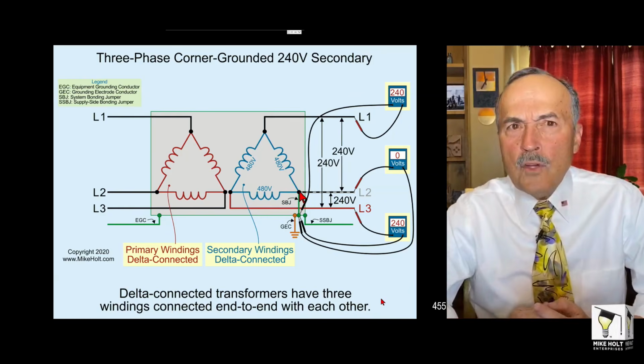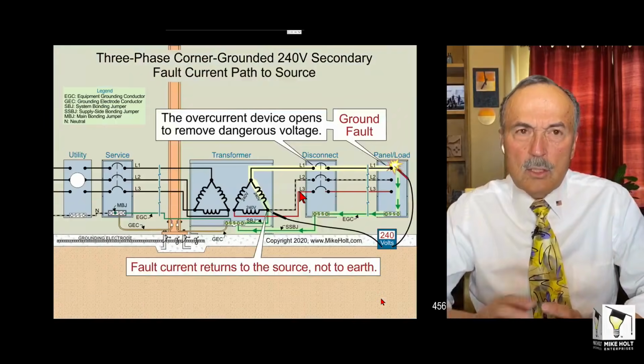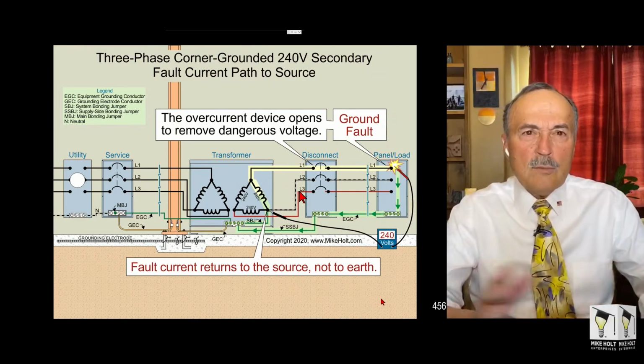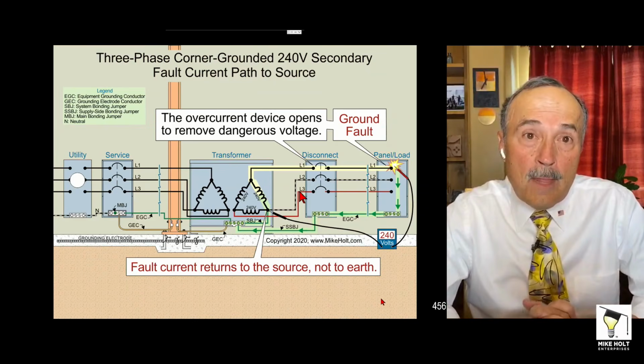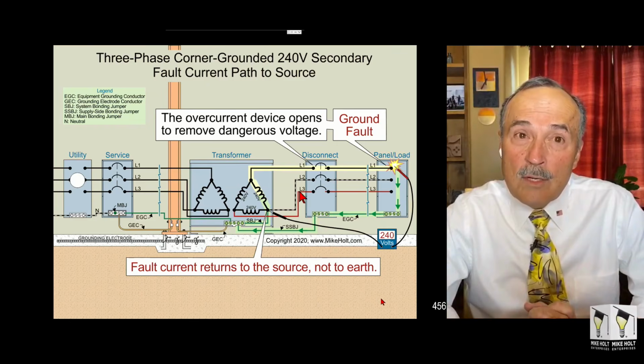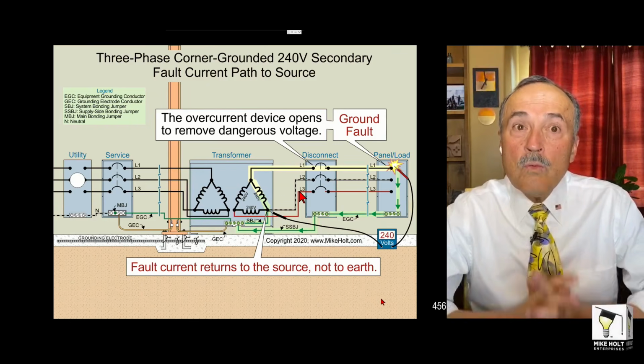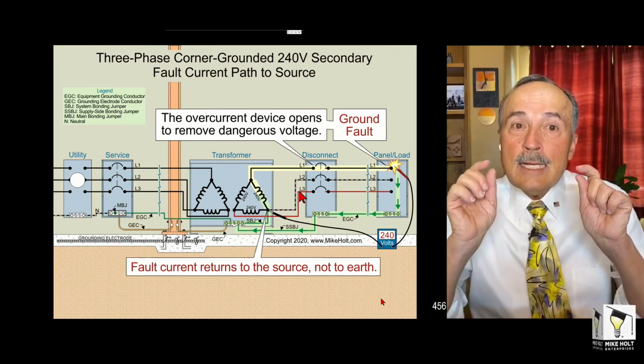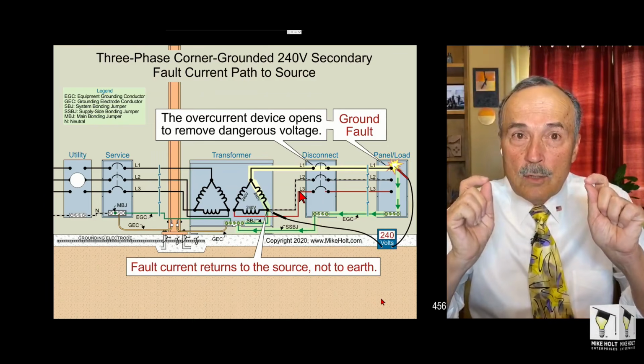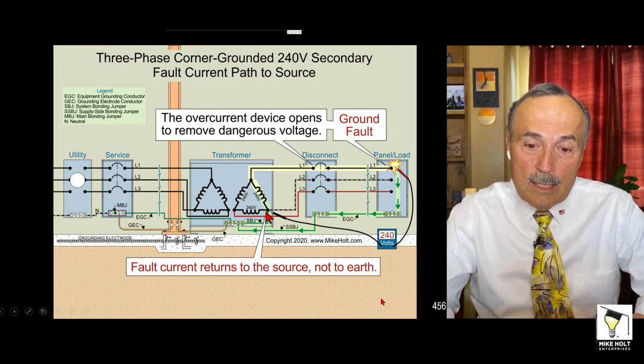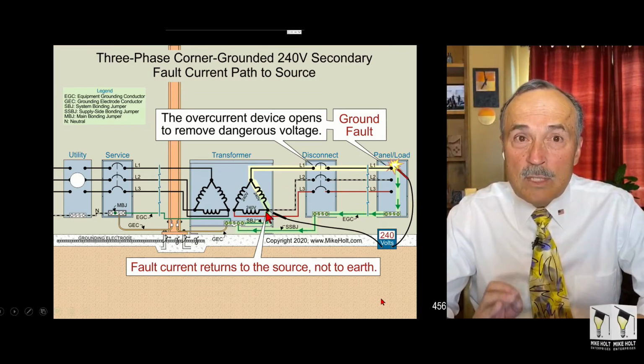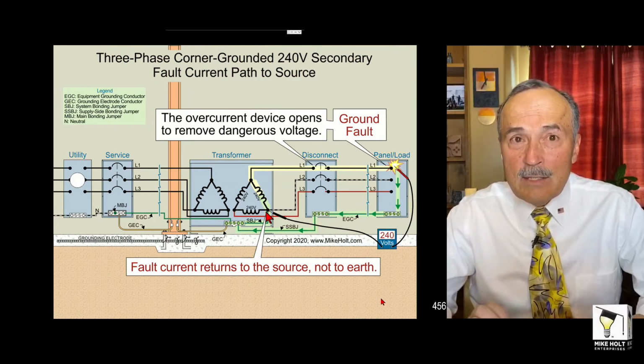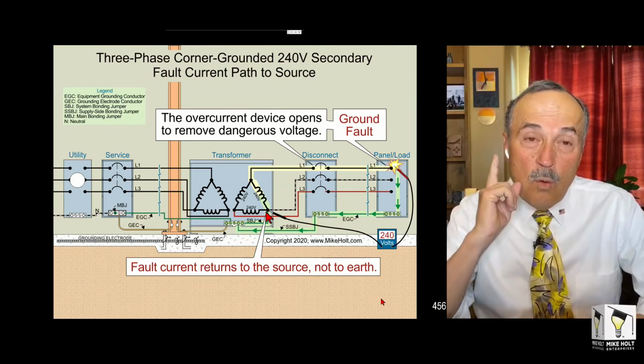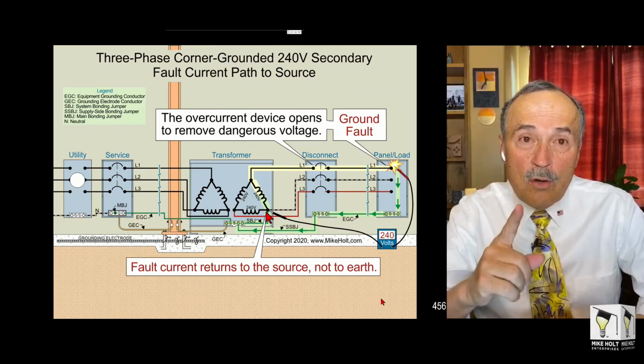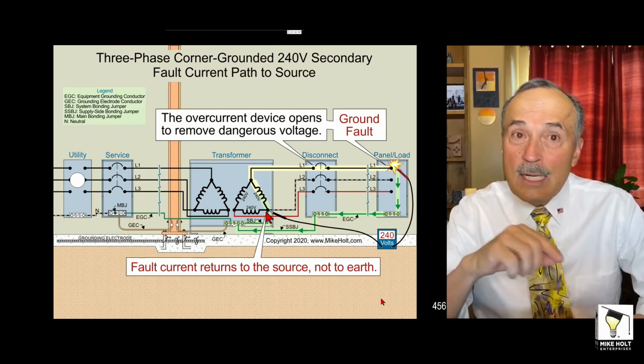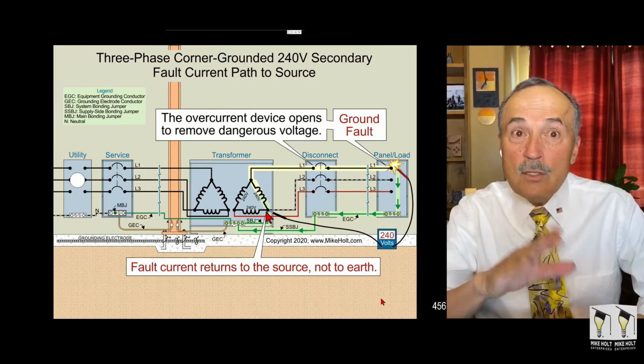Somebody said, well, Mike, you know, if you grounded that corner grounded delta system, aren't you going to have objectionable current flow? Guys, you can only have current traveling on metal parts when it's connected to the grounded conductor at 2 points. Look what we did here on this corner grounded delta system. How many times did we ground that secondary system and bond it? Once. Whether you corner ground it, whether you center ground it, it doesn't really matter. You can't do more than one.